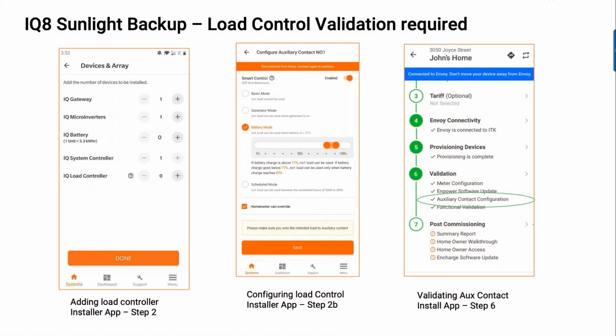For load control for sunlight backup, you have to configure a load controller. The way we know that you're doing a sunlight backup system is that you'll have 0 batteries. You would have 0 in this field, and you would need a load controller. When you're doing load control, you need to configure that load control. If you remember, we talked about this a little earlier. If you're doing any kind of load shedding, you should configure this early so that it smooths your path to installation. If you don't, you're going to be going back and redoing something, and it's going to stall your time on site. So if you're installing sunlight backup and load control, make sure you configure the behavior of the load control accordingly.